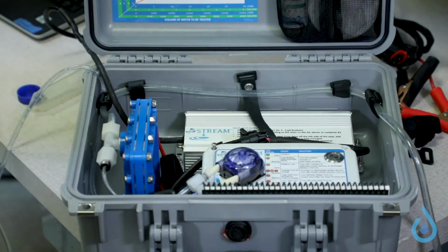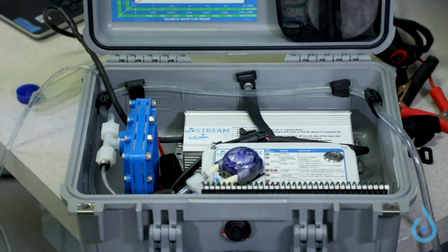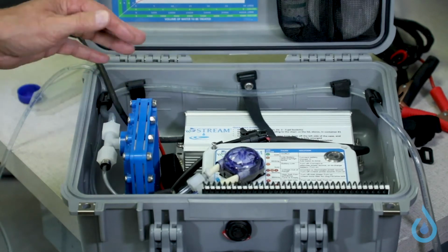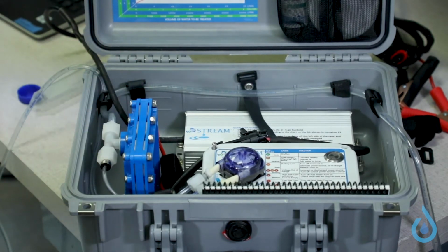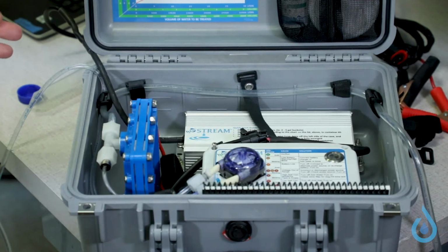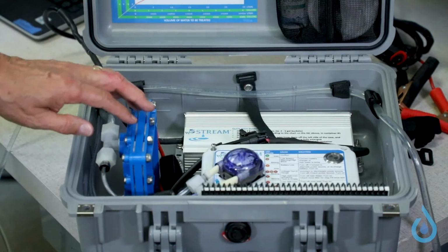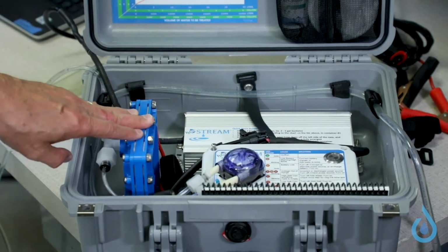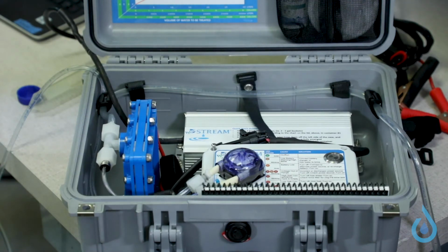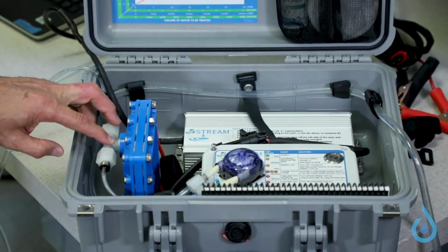Scale occurs two different ways. One is in the salt. So calcium contaminants may be in the salt itself, and that's a source of calcium carbonate scale to form in the cell. And the other is using hard water, water with a lot of hardness, a lot of scale in the water. And both of them, when they get into the cell and electrolysis is occurring, there are conditions at one of the electrodes, the cathode electrode, where scale will form. And it can accumulate over time and ultimately cause restriction in the flow out of the cell.